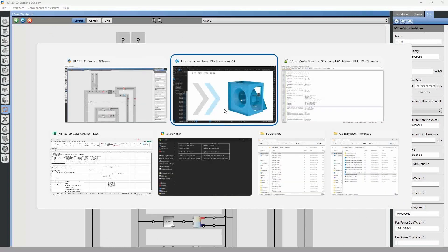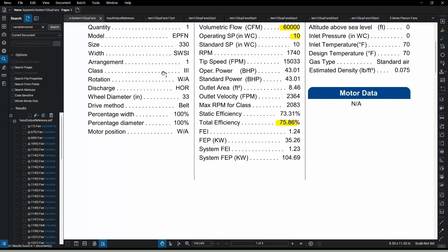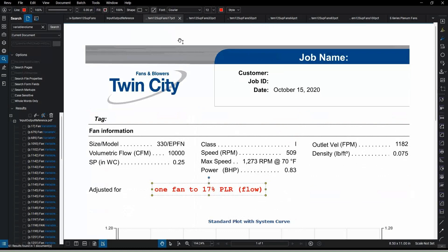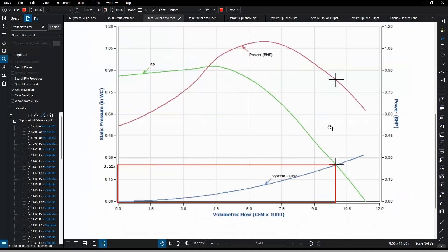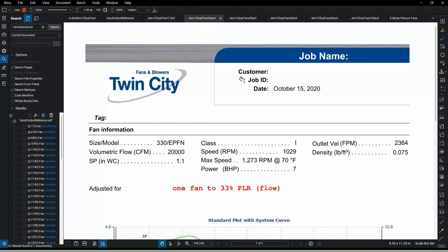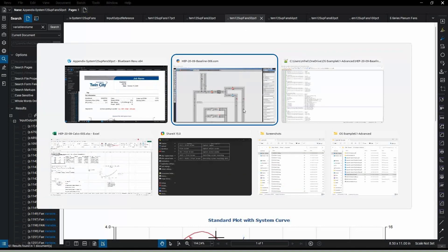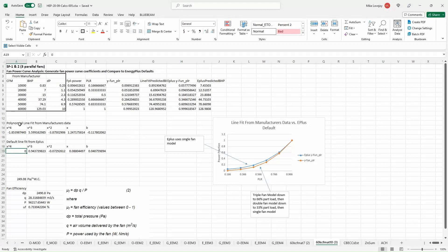And to do that you need to have some data first. So the performance of the fan and then some curves, some fan curves of the fan or fans running at various different percentages of airflow. And then you can construct a new fan curve using a line fit algorithm in Excel.